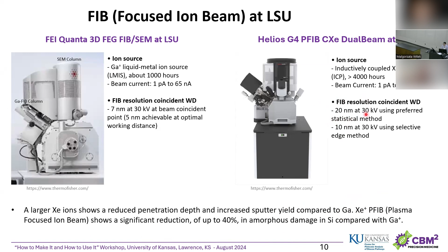In order to understand what parameters you have to control to produce the structure you want to build with FIB, I don't want to go into detail, but I think it's good to understand the basic structure of the ion column. It's a very complicated system, but here you have the ion source, where the ions, from the liquid ion source, gallium or xenon, are produced. Then you have the extractor, where you apply a high voltage so that you direct those produced ions towards the sample.